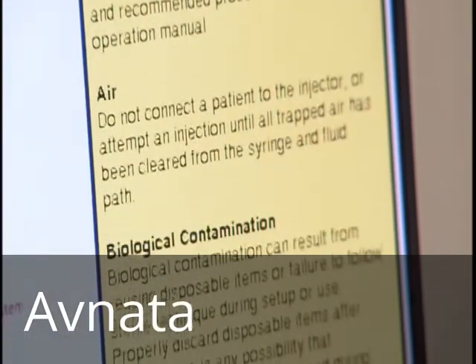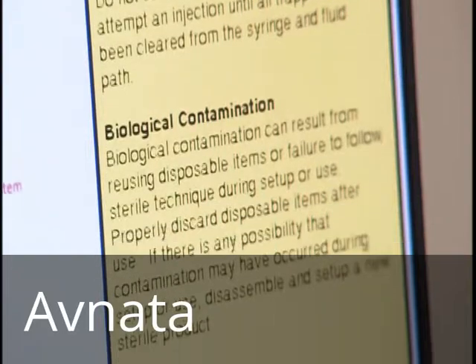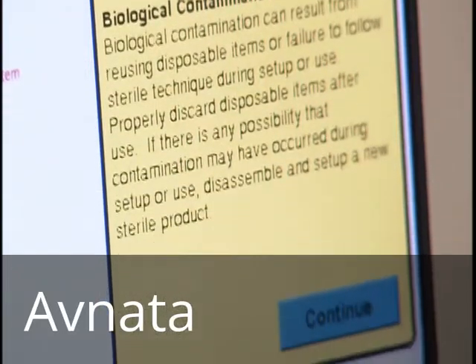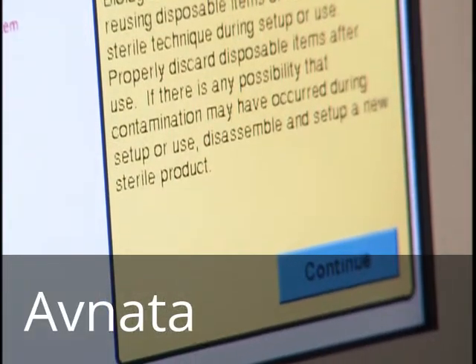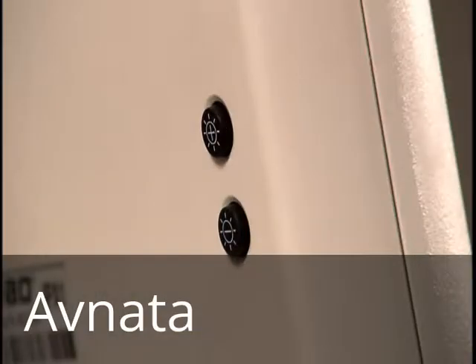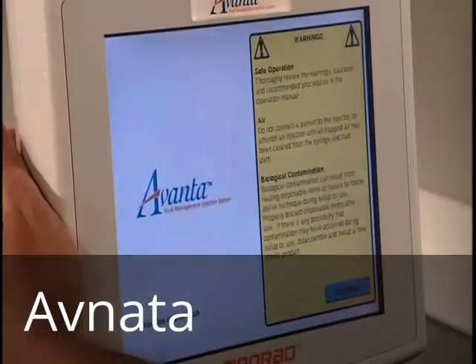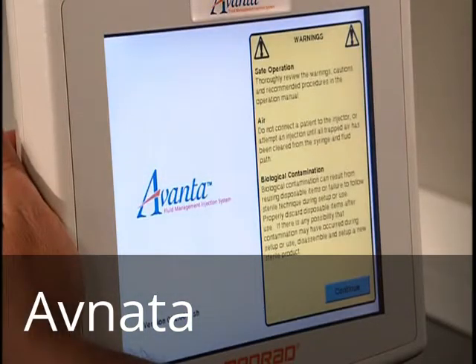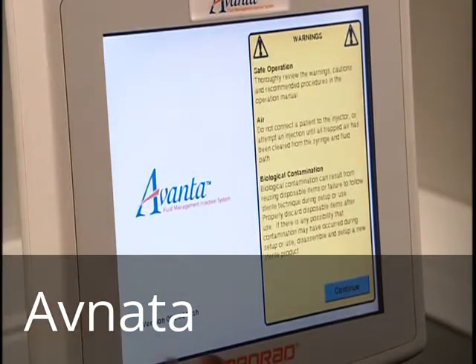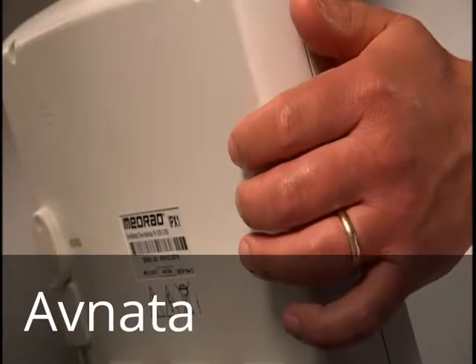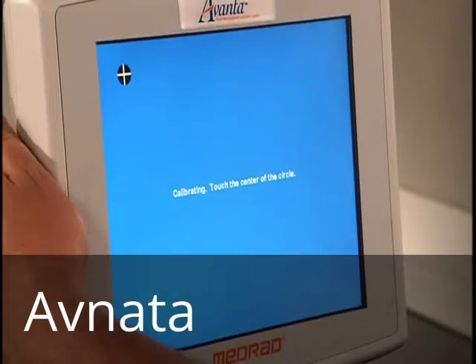If the safety screen indicates a system error, verify that a patient is not connected, record the code, and contact MedRad service. To adjust the screen brightness, press the controls located on the back side of the DCU. The user may calibrate the touch screen when the safety screen appears. Press both brightness keys simultaneously, then follow the on-screen instructions.